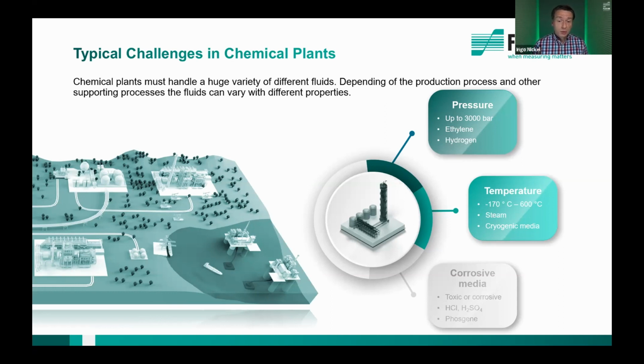The third part are corrosive media. If the media is highly corrosive, like sulfuric acid, hydrochloric acid, nitric acid, or other corrosive media, the selection of the wetted part or the wetted material is very important. And for highly corrosive media, you have to select between expensive MOCs like Hastelloy or tantalum, but with Flexim's approach of having non-intrusive flow measurement solutions, we are completely independent from these demanding conditions, and all critical conditions can be covered perfectly with our clamp-on flow meters.